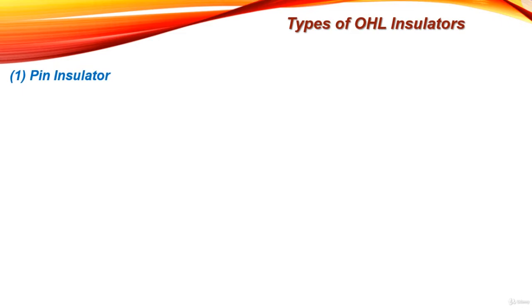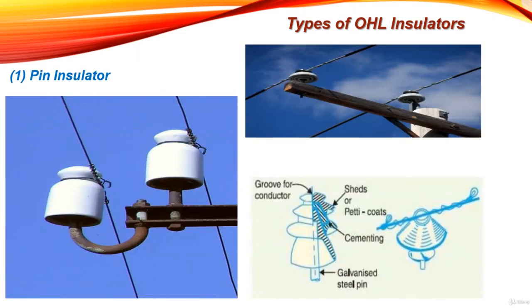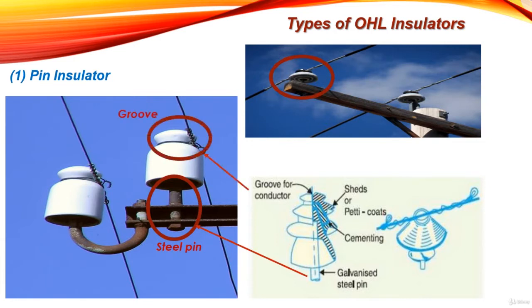The pin type insulator consists of non-conducting materials such as porcelain, glass, or polymers. As the name suggests, the pin type is secured to the cross arm on the pole using a steel pin. There is a groove on the upper end of the insulator for housing the conductor, and cement is used to fix all steel parts with the insulator material like porcelain or glass.